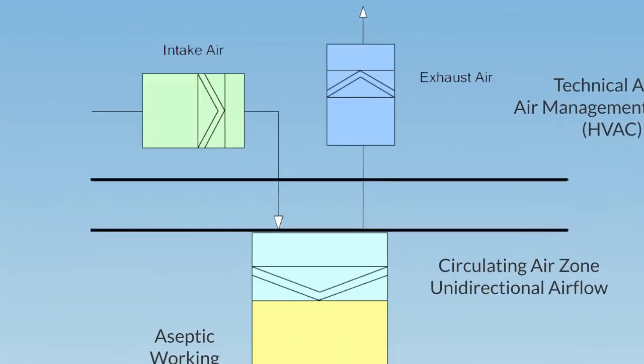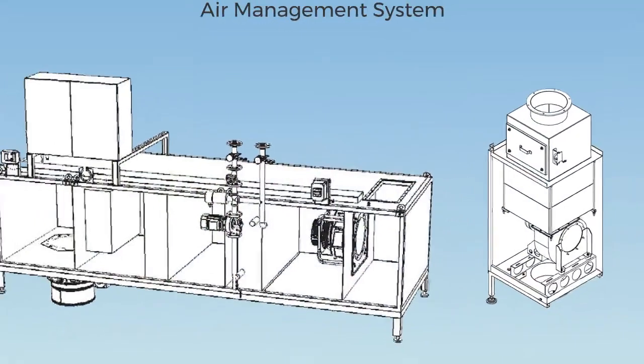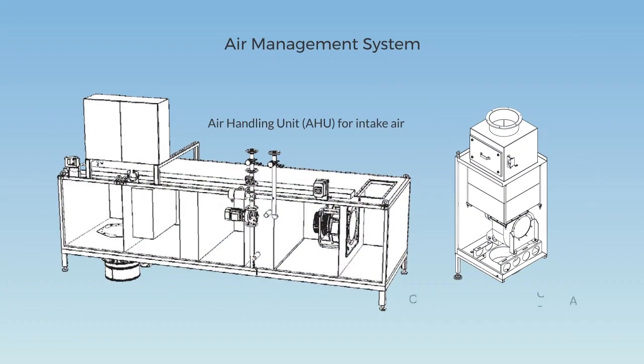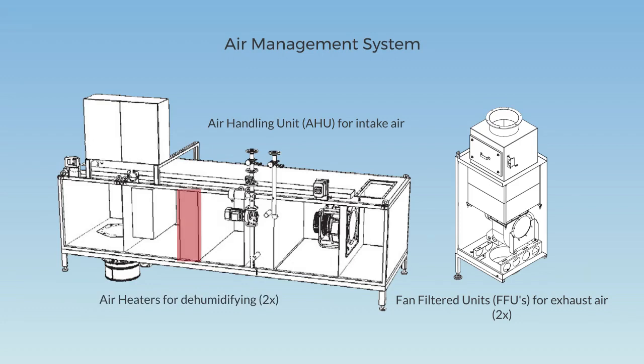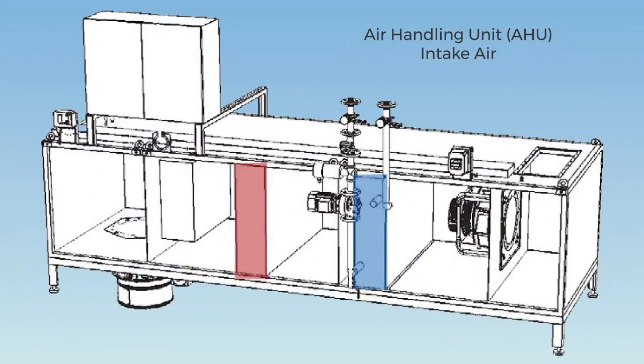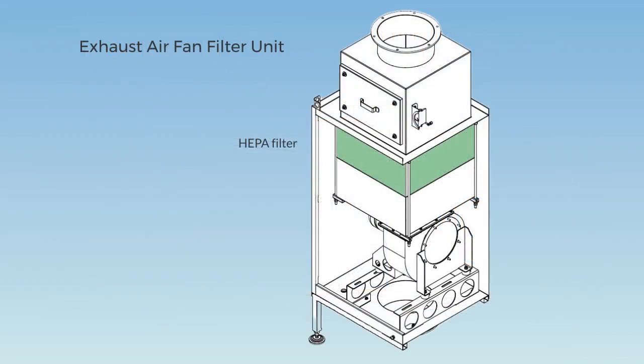The air handling equipment in the technical area includes an air handling unit for intake air, 2 filtered fan units for exhaust air, and 2 air heaters for dehumidifying the chamber. The intake air handler is equipped with an air cooler, air heaters, HEPA filter, circulating fan, and related sensors and gauges to ensure and control the temperature, relative humidity, and positive differential pressure in the isolator chamber. The exhaust unit also has a HEPA filter and a pressure gauge for measuring the differential pressure across the filter.